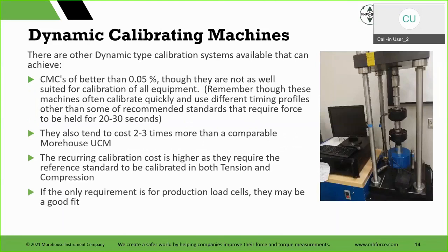Then we start dealing with another machine, these dynamic cal machines. Manufacturers are making them. Not a bad machine, but you're typically looking at CMCs of better than 0.05, not as well suited for calibration of all equipment. Often they calibrate quickly, which is a big plus, but then they don't hold the forces. So a lot of standards, ISO 376 requires that the force is held for 20 seconds or more. They also tend to cost 2 to 3 times more than a comparable UCM. The recurrent calibration cost is higher as they require the reference standard to be calibrated in both tension and compression. So our UCM has standards in compression only, while these are compression and tension, which carries a higher ownership cost.